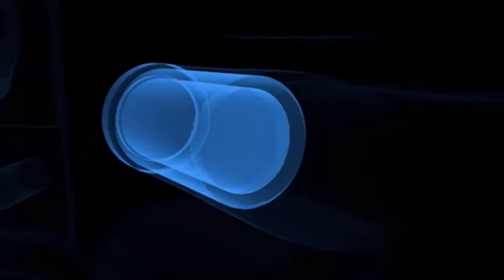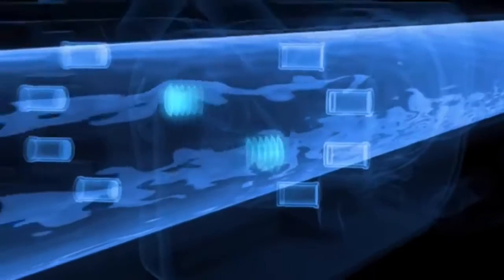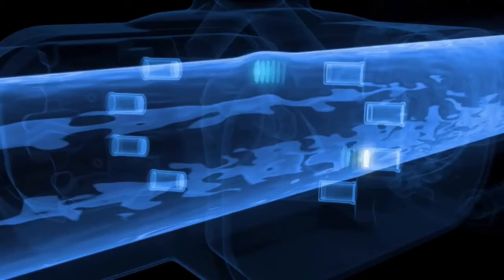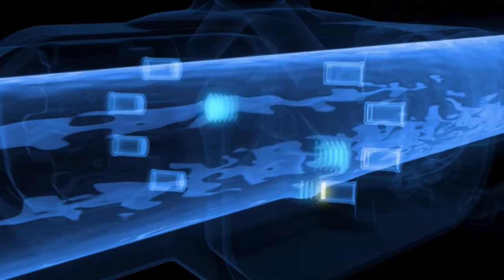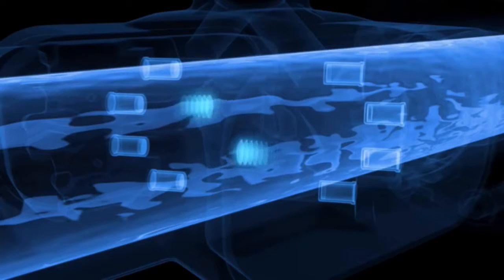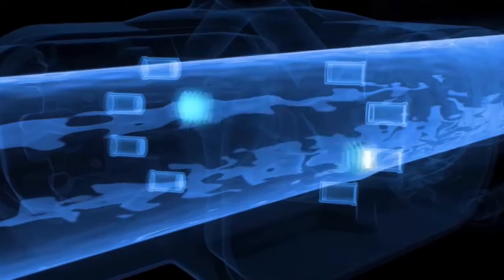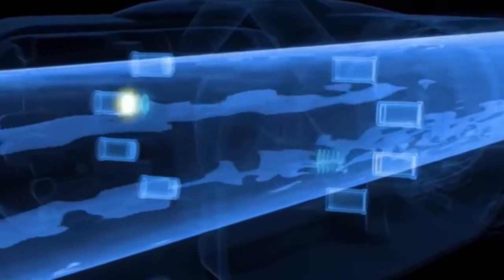By increasing the number of sensor pairs, it is possible to accurately detect flow profile distortions over the entire pipe cross-section. When there is no flow, the signal times are the same upstream and downstream. Once the fluid begins to flow, the ultrasonic signals begin to accelerate in the direction of the flow and slow down against the flow. As a result, the ultrasonic signals have different transit times, less time with the flow and more time against the flow of the liquid.